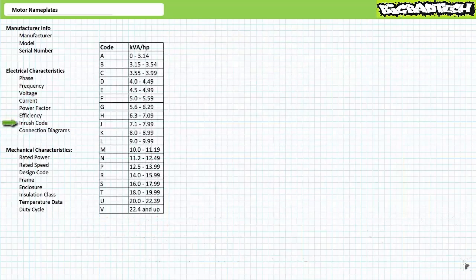Inrush code, or kilovolt amperes per horsepower code, or just plain code. In the event the motor nameplate doesn't explicitly specify LRA, or locked rotor amperes, this is a letter code which can be used to estimate inrush current experienced upon closure of a full voltage or direct online starter. As I mentioned previously, the initial inrush surge can be several times full load conditions and must be accounted for. Luckily, inrush conditions don't last for long, and once the rotor comes up to rated speed, current levels out.